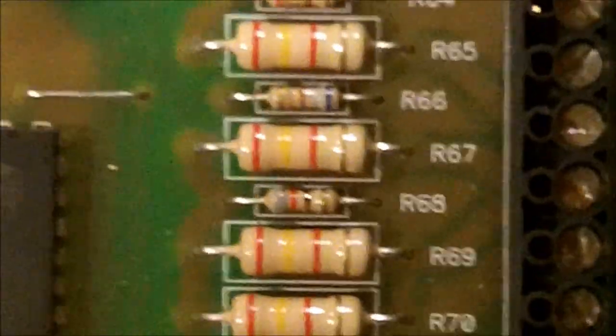So right now everything is open. Thermostats have time delay on it. The board has a 3-minute time delay on it, so it's saying zone 1 is open, zone 2 is open, and so now what's going to happen is when the thermostats do call, it's going to send a signal from the thermostat. It's going to go through the circuit board, go through the different relays, and send power out of Y1 down.